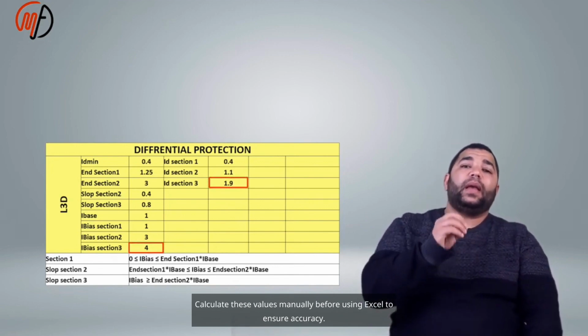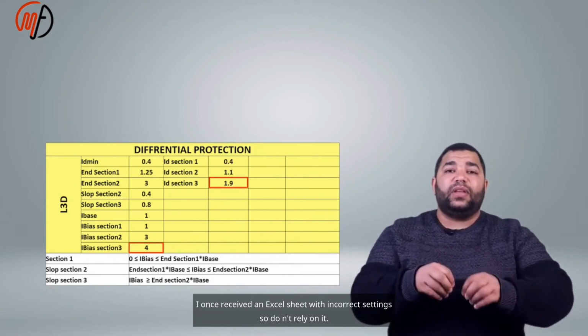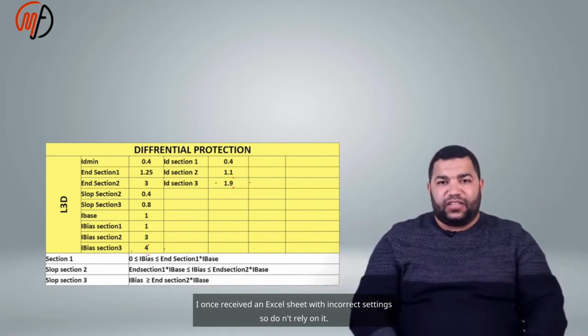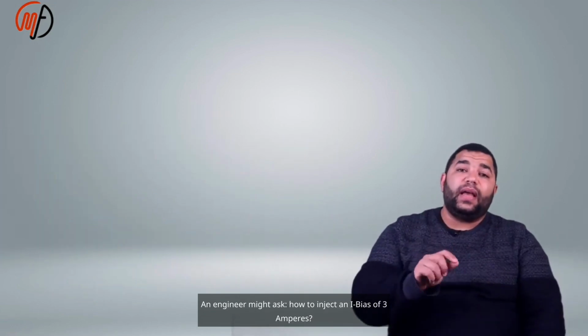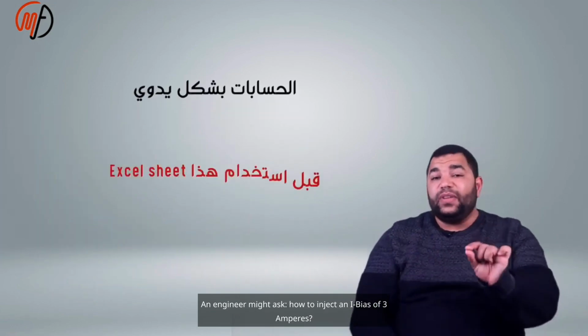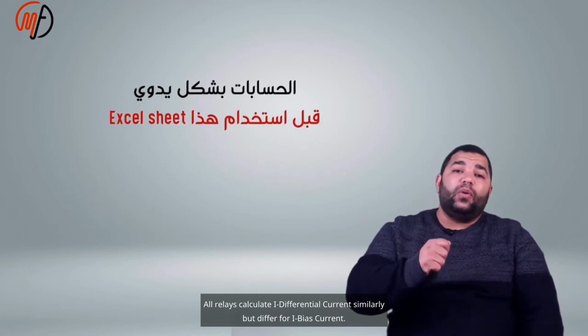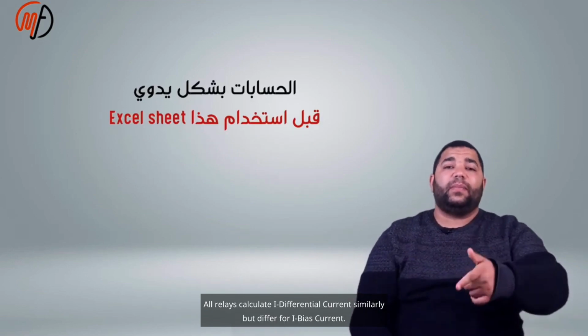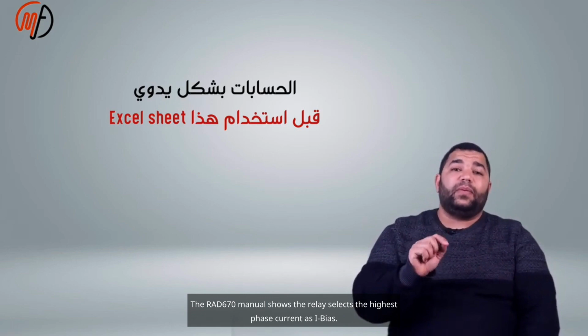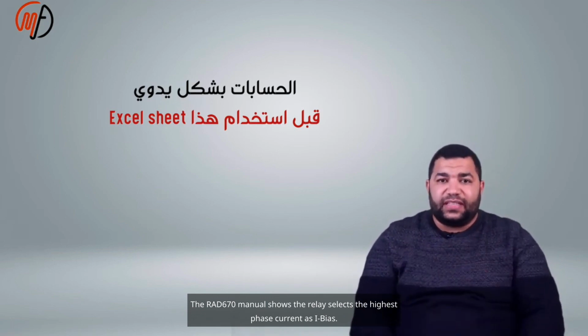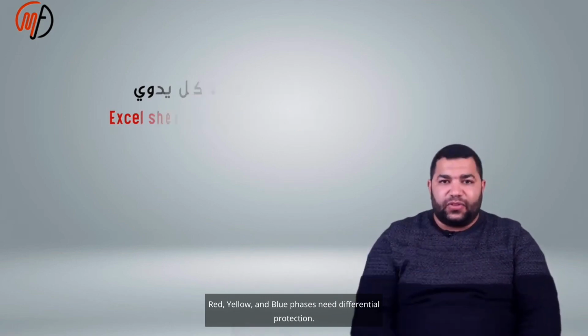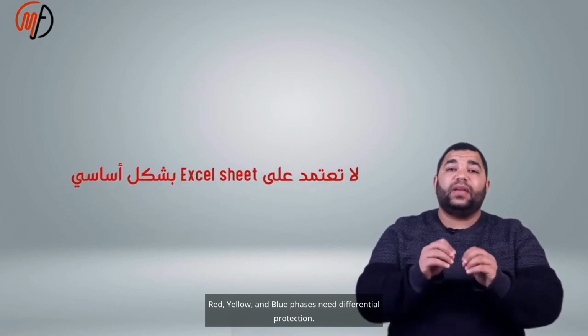Calculate these values manually before using Excel to ensure accuracy. I once received an Excel sheet with incorrect settings, so don't rely on it. An engineer might ask how to inject an I bias of 3 amperes. All relays calculate I differential current similarly, but differ for I bias current. The RAD 670 manual shows the relay selects the highest phase current as I bias. Red, yellow, and blue phases need differential protection.